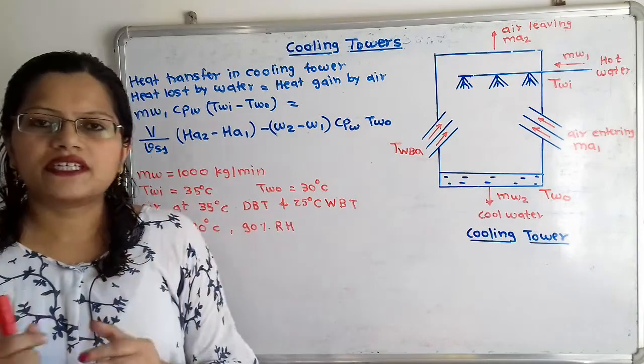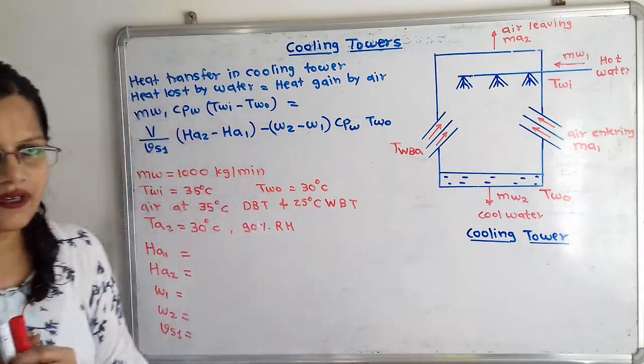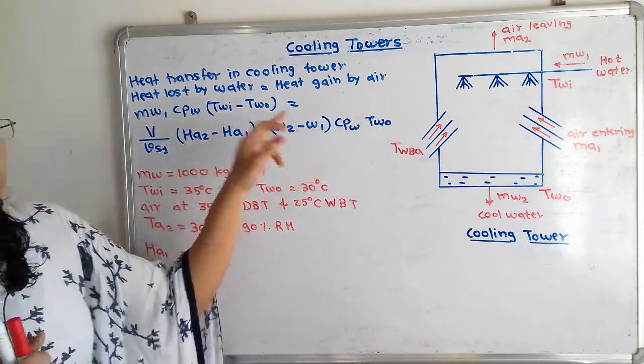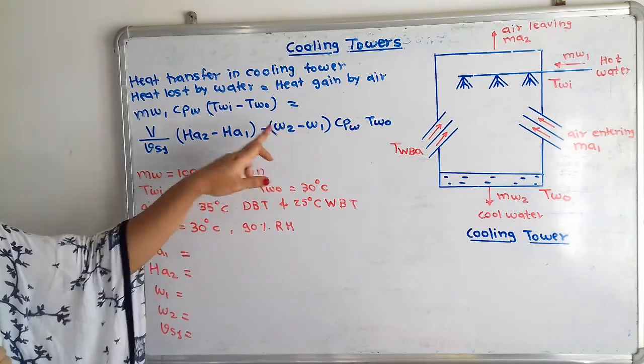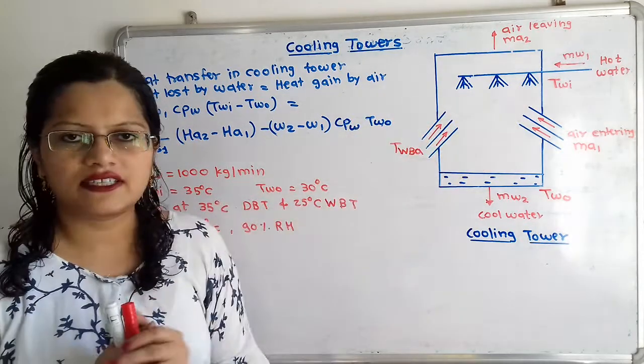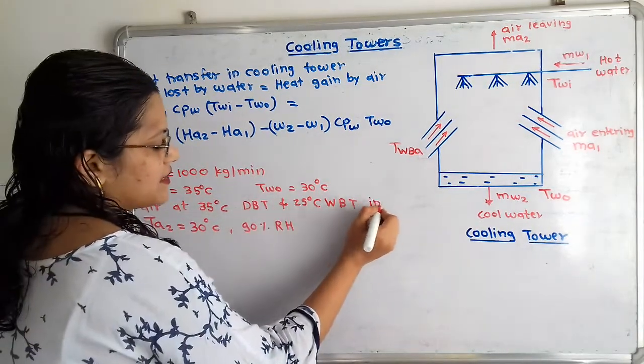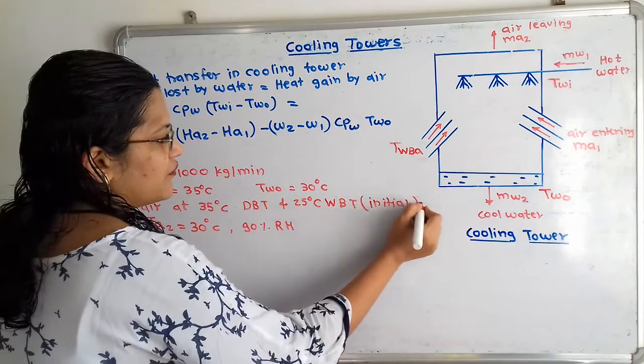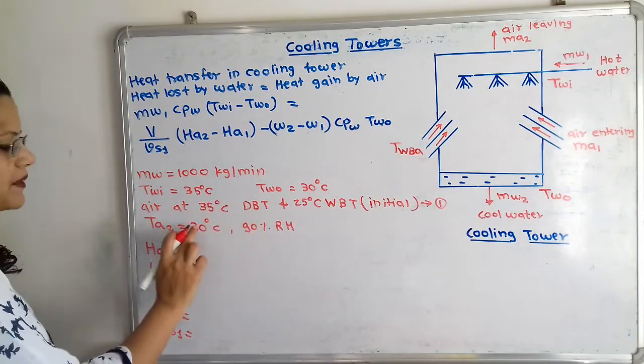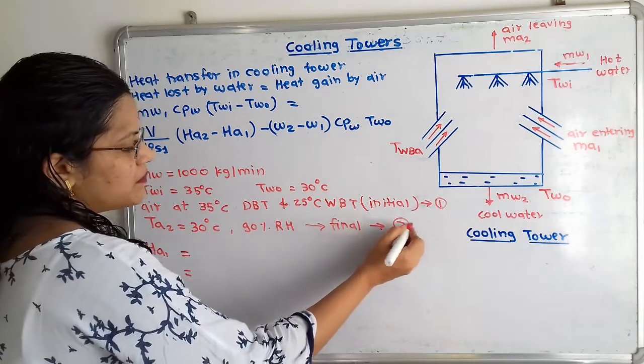To use the psychrometric chart, we first plot point 1 for the initial condition of air and point 2 for the final condition of air. From point 1 we find specific volume, enthalpy, and specific humidity. From point 2 we find specific humidity and enthalpy. The initial condition is 35°C dry bulb and 25°C wet bulb temperature. The final condition is 30°C dry bulb temperature and 90% relative humidity.